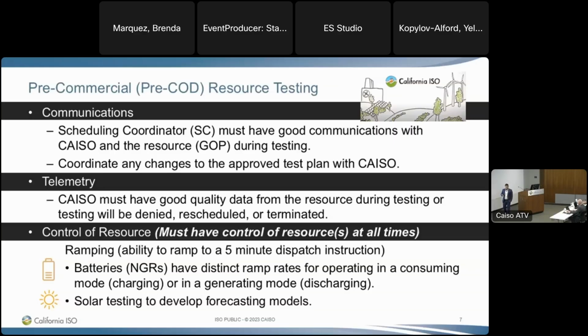If you are testing above that 100 megawatts and it's 500 and you're causing a congestion issue, we will terminate that testing until further notice. So we don't really want to have to do that to you. We understand you're testing, you want to be getting COD. We want to help facilitate that process. So good communication is key.